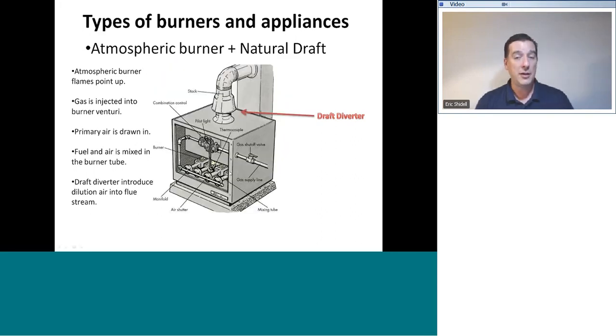On a boiler, also a very common source of an atmospheric burner. Flames pointing up, primary air joining in the burner, secondary air joining the flame already in progress, draft pulling combustion products up through the heat exchanger, joining the flue, which is also under negative pressure, and room air joining under the bell here to join the flue for dilution air.